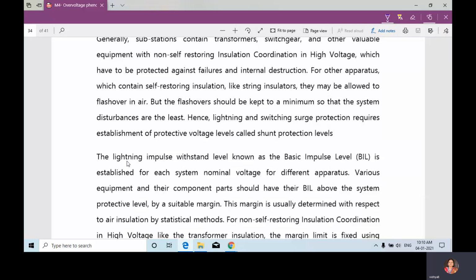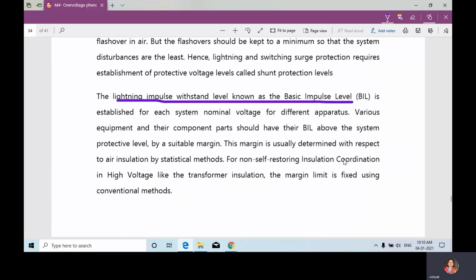Next, the lightning impulse withstand level is known as the basic impulse level. It is established for each system nominal voltage for different apparatus, various equipment and other component parts should have their BIL, basic impulse level, above the system protective level by a suitable margin. This margin is usually determined, with respect to air insulation, by statistical methods. For non-self-restoring insulation, like the transformer insulation, the margin limit is fixed using the conventional method.